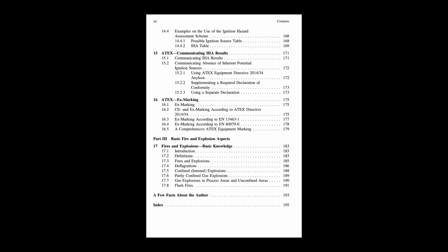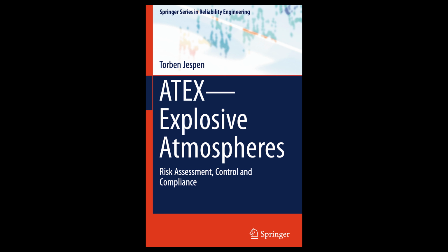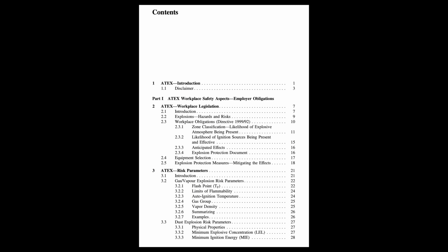And the guide gives a practical example of CO2 inerting. Yeah, a good one is in coal grinding facilities, like you find in cement plants. During normal operation, they might use waste gases to keep things inert. Okay. But during shutdown or startup of the coal mill, those are high-risk periods for dust explosions or smoldering fires. So injecting an inert gas like CO2 is often used as an extra safety measure during those specific times. Makes sense. Those transitions, start-stop, often seem riskier.